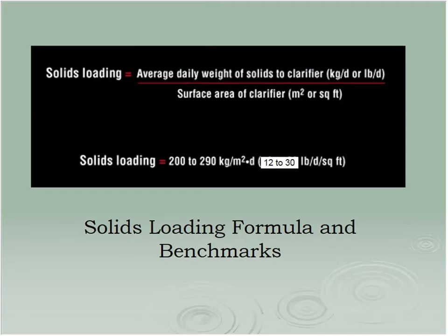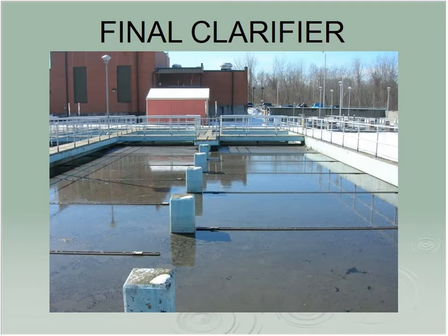And here we do have to be concerned with solids loading, 12 to 30 pounds per day per square foot recommended. Well, if mixed liquor is running way too high for some reason, it's not going to settle out. I experienced this when I took over my plant. They used to run ridiculous mixed liquor numbers. We couldn't settle it for love nor money. Way too high. That's a concern on this one.